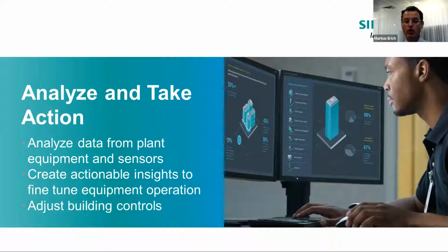We deployed variable frequency drives at condenser pumps, chill water pumps, and cooling tower fans, which allowed the software to run the system - as the name says, Demand Flow - very tuned to the demand. We tried to establish a very linear way of dispatch and operation, and that's where the savings are generated. As a result, the system reduces flow during periods of reduced demand, and can lower operation and maintenance costs significantly.